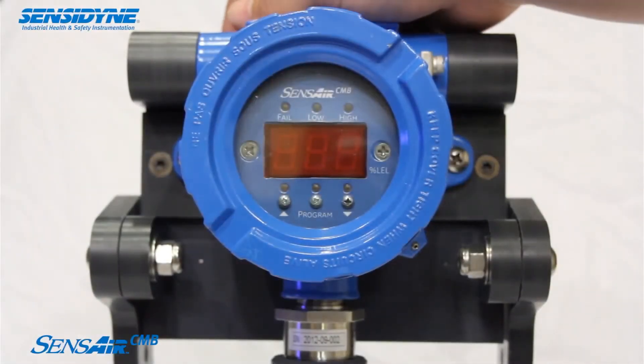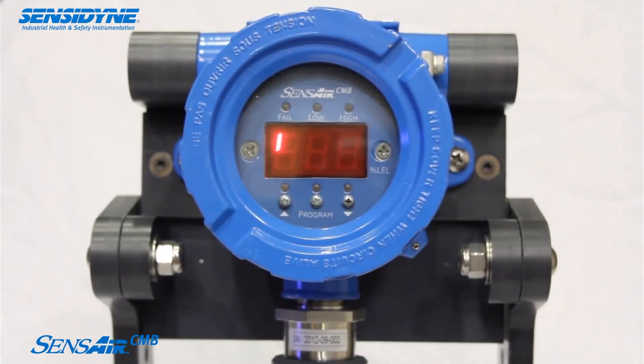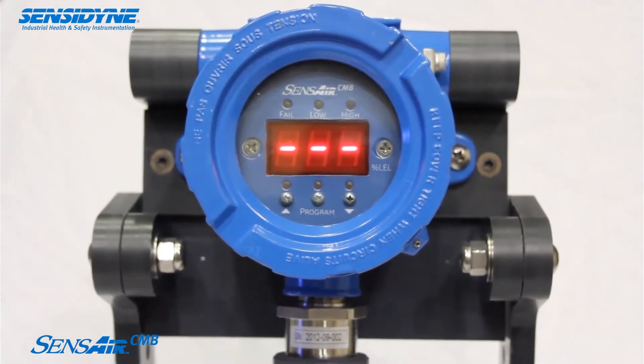The SensAir CMB is a heavy-duty combustible point gas detector designed to be poison-resistant. Sulfides and silicones are known to poison, or inhibit, standard catalytic bead sensors at concentrations as low as one part per million. Poisoned catalytic bead sensors are rendered ineffective and unable to detect gas.